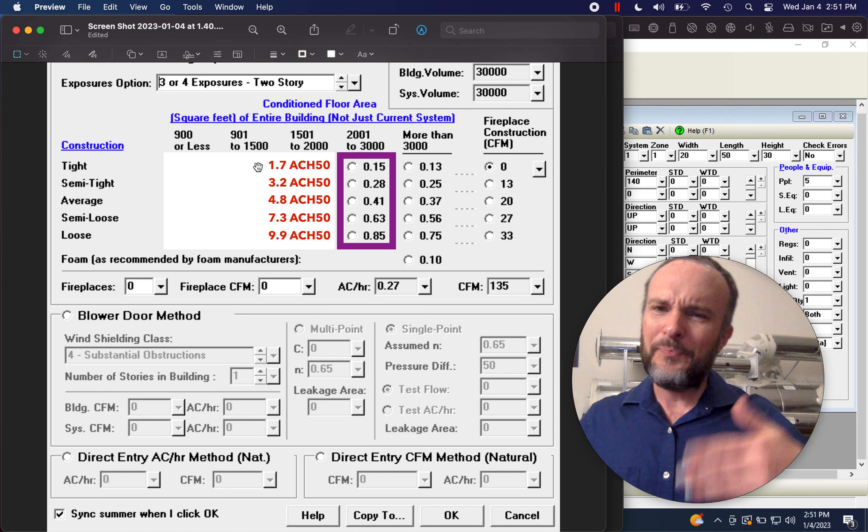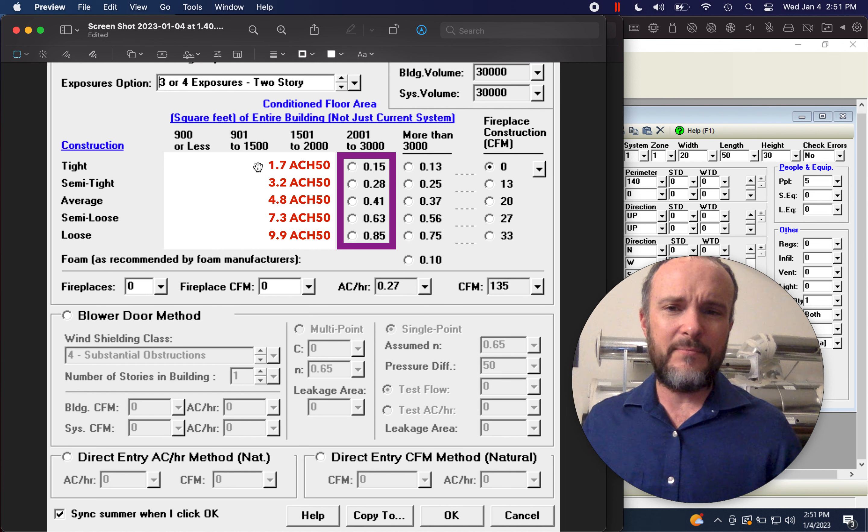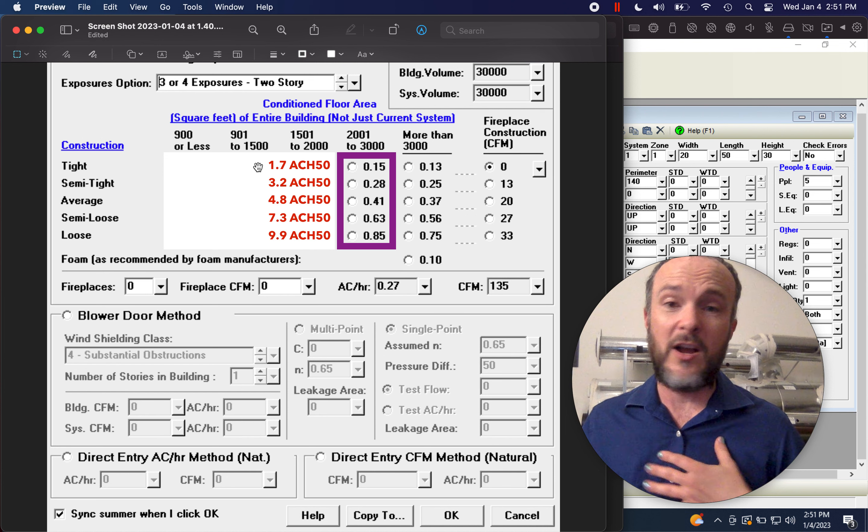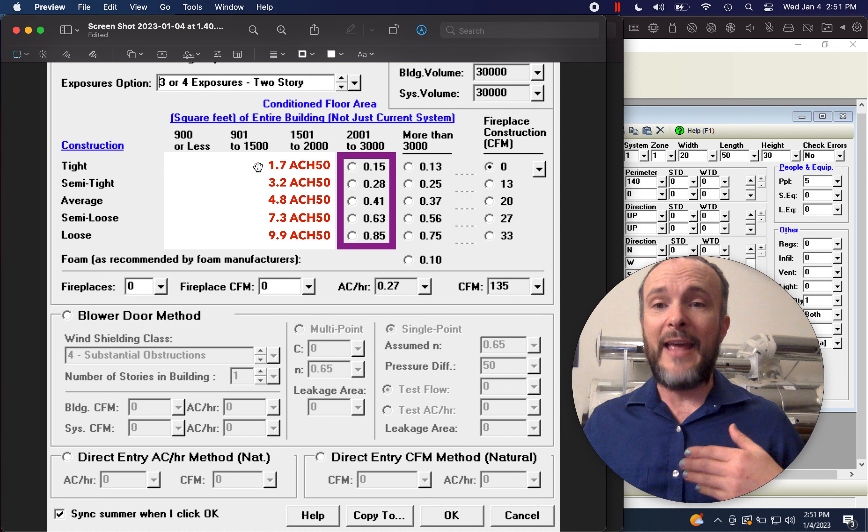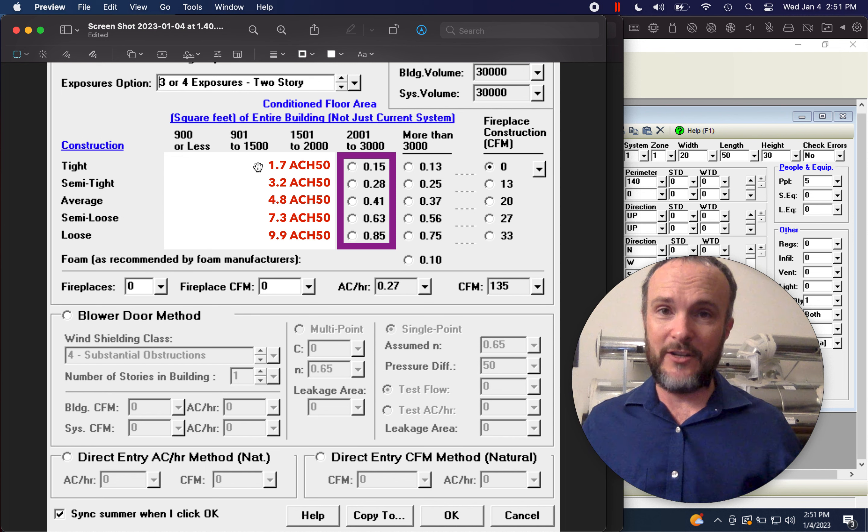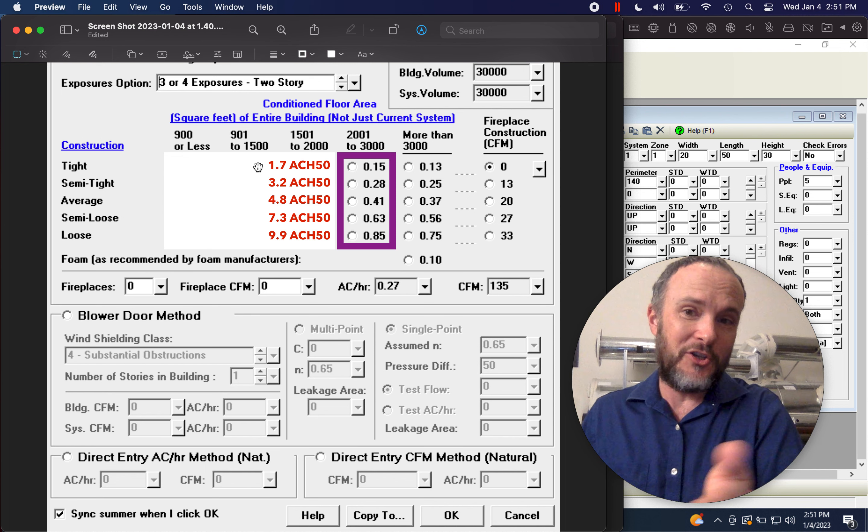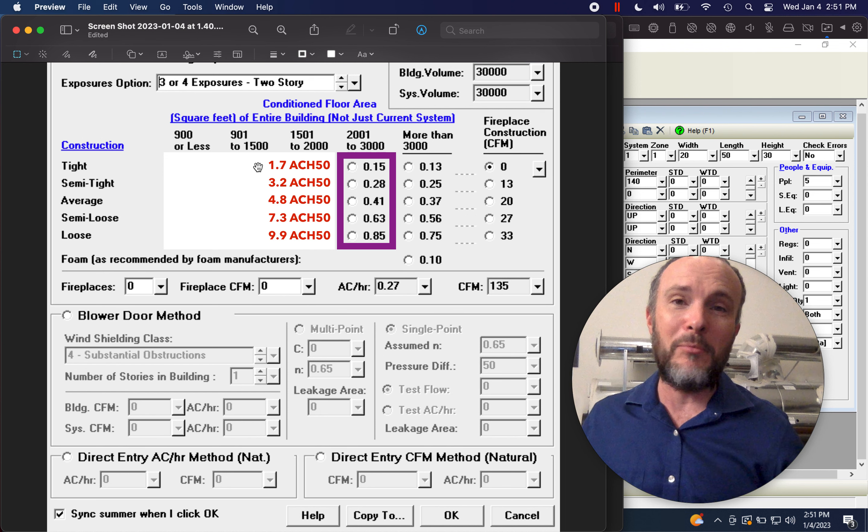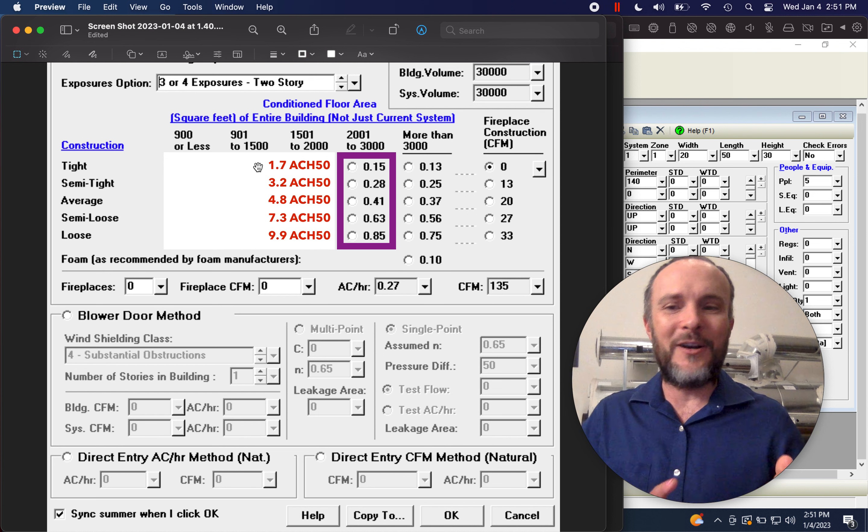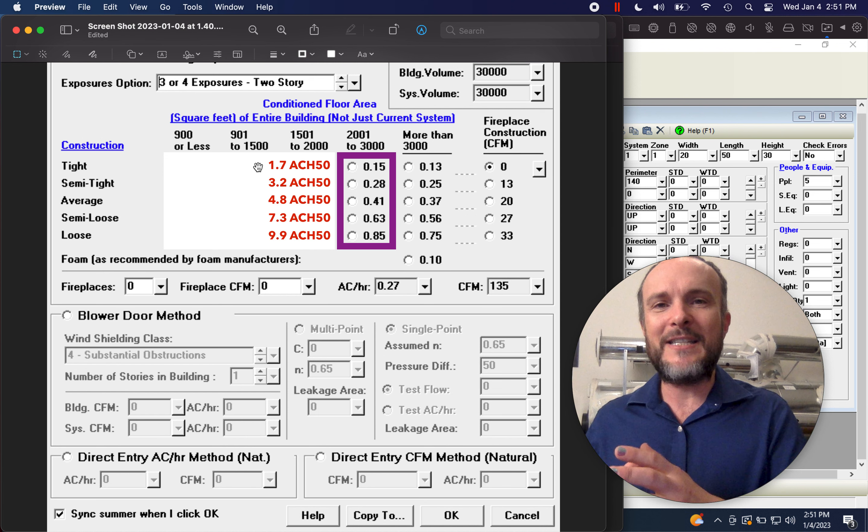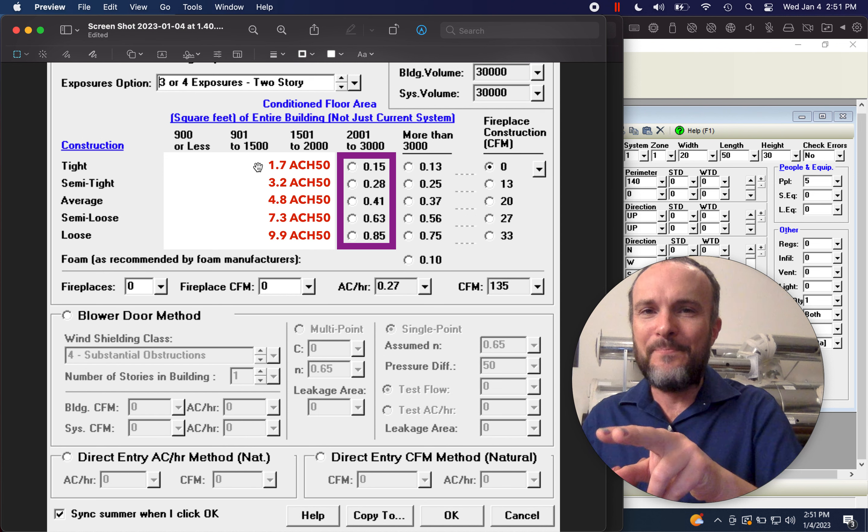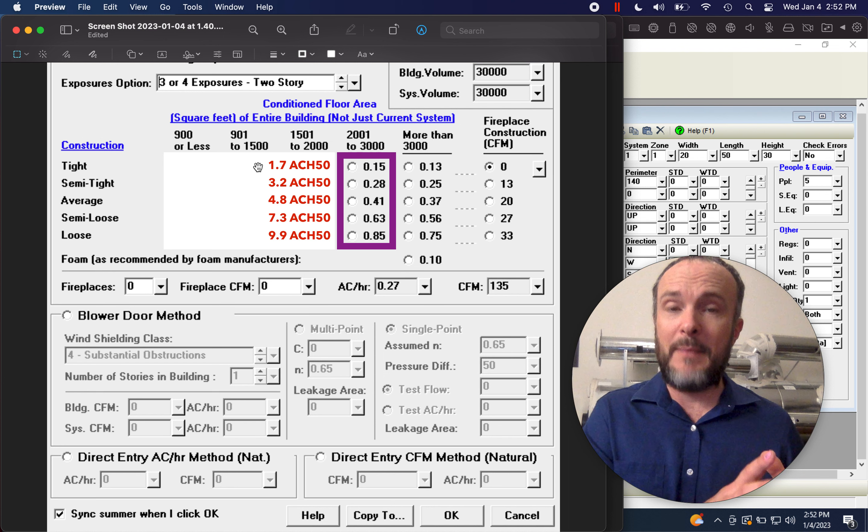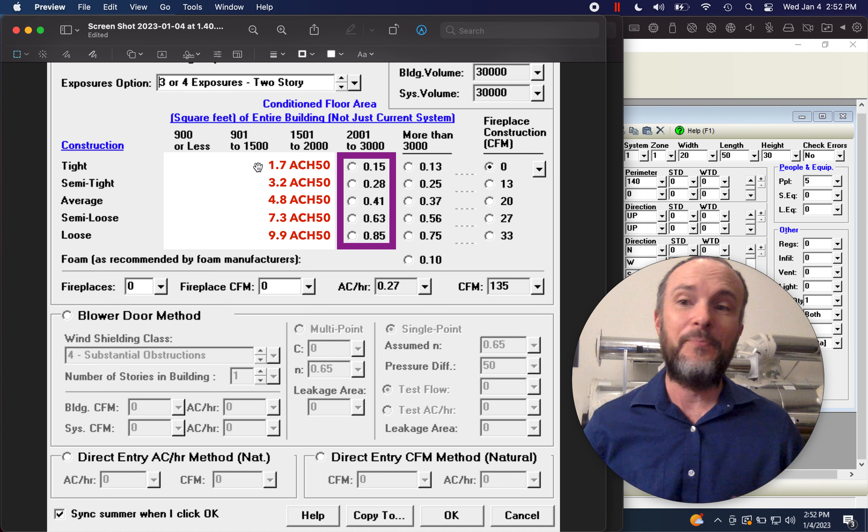We almost double to 3.2 for a semi-tight. And I would say that those like for average builders, those are okay estimates. I don't think that they're that okay for reasons that I'll get to in a second. Average about five ACH 50 that is required by code in many states across the country. Five air changes per hour is like the code maximum for air leakage at that point. Semi-loose seven and loose. Those are like, who knows what's going on there? Because honestly, I've lived in homes that had way more than 10 ACH 50. So saying that loose is the loosest it gets is like, no way I could, I bet you could double that on a lot of older homes.